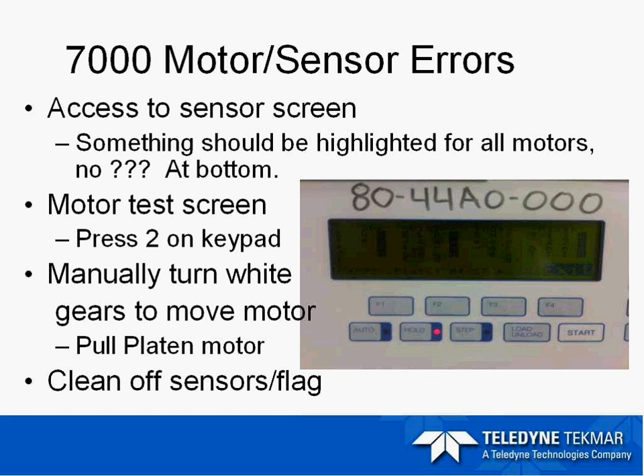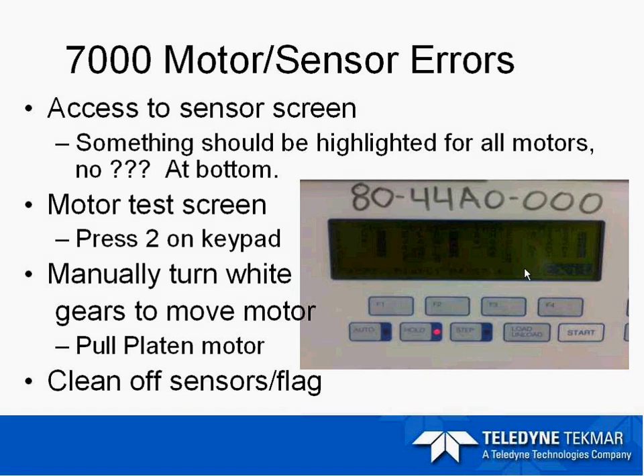At the bottom of the display on the 7000, you may notice question marks, which indicate that the carousel is not installed or there is possibly a problem with the encoder emitter board for the carousel. You will also note that there is a star after the platen position indicator. The star is not necessary for proper function of the instrument — just no question marks — but it does indicate that the carousel is centered in the position it needs to be. Something should also be highlighted for each one of the columns shown for sample, vial, index, and mixer. There will be nothing highlighted for the indexer if you do not have a carousel installed.